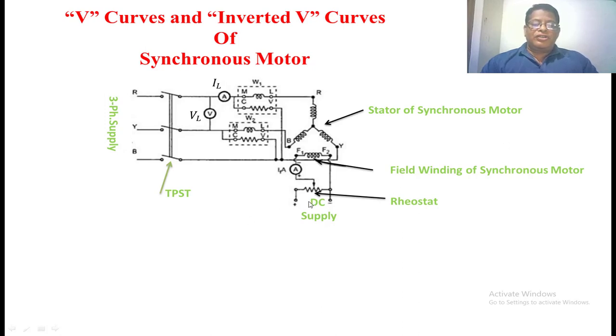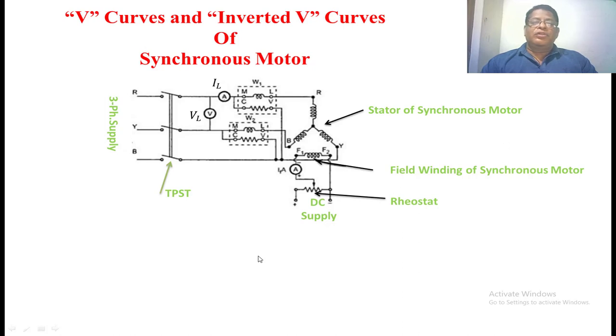By changing the potential divider, the field current passing through the synchronous motor will be changed. By changing the field current, the armature current of the synchronous motor will change. We note down the readings of the voltmeter, ammeter, and wattmeter. In this manner, we take 10 to 15 readings. We are conducting this test at no load only, but in a similar manner we can conduct the same test at half load and full load as well.